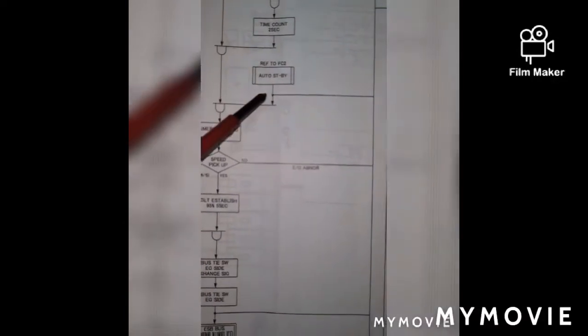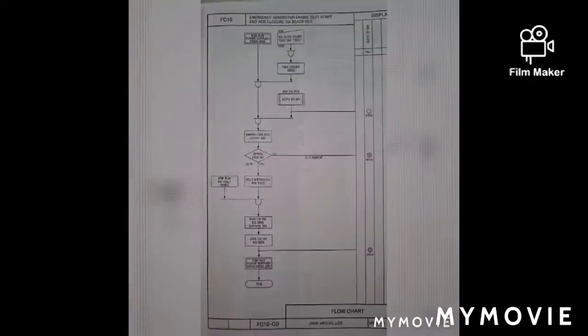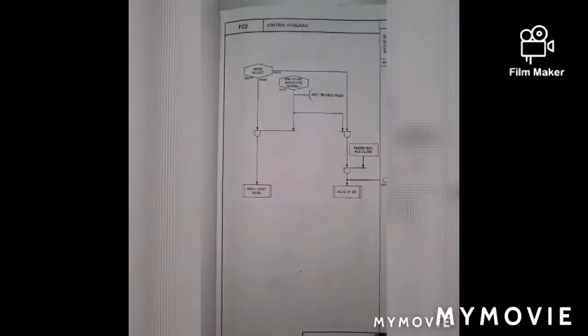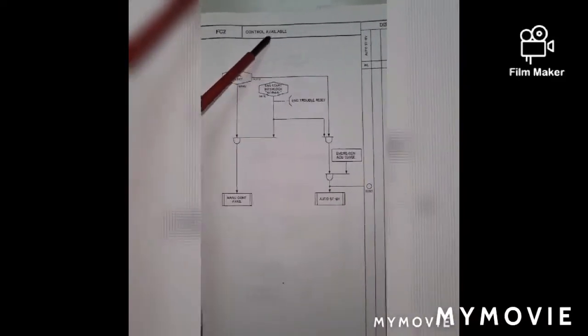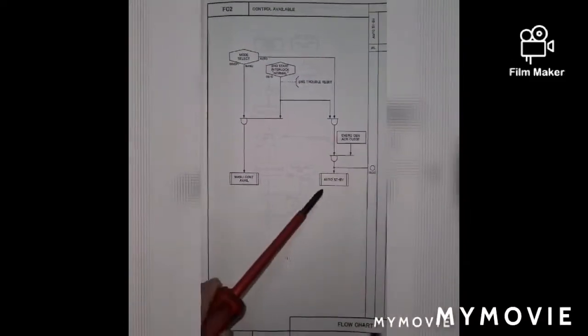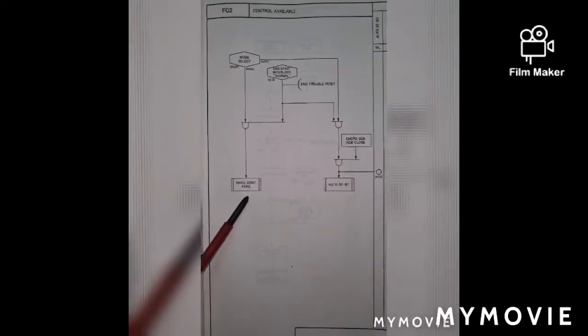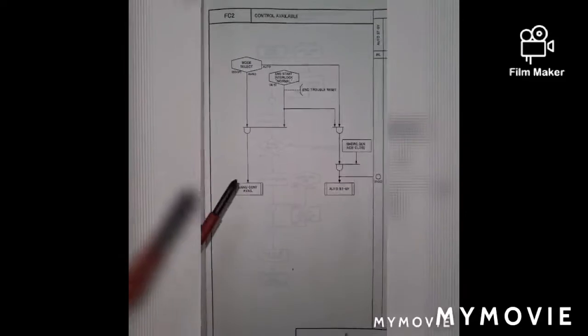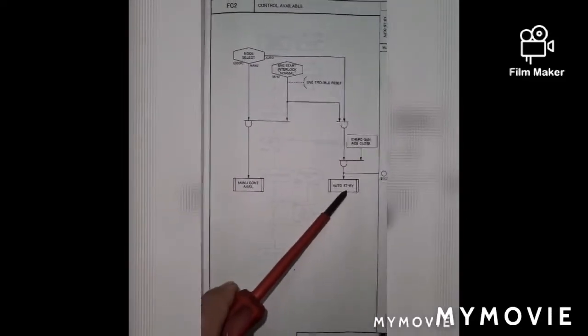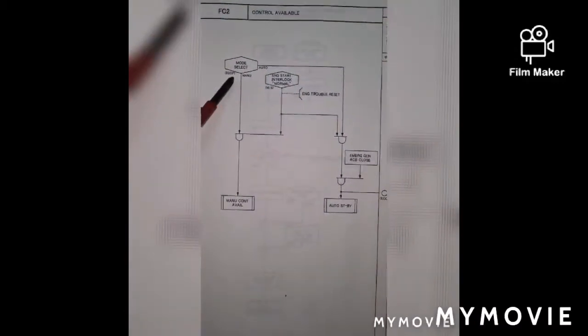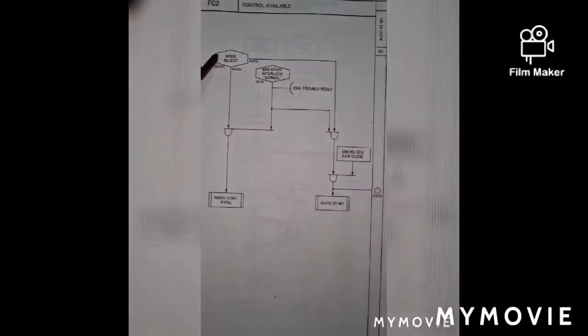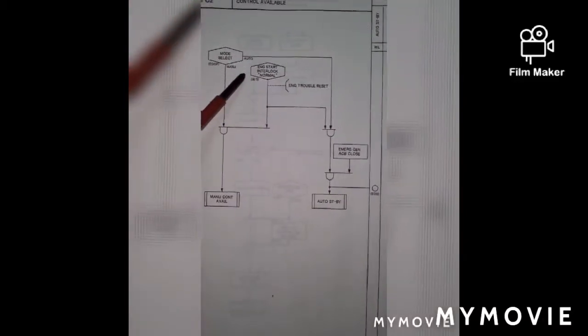As you can see here, there is the reference to FC2. This means that for FC2, you need to satisfy the condition that your emergency switchboard control and emergency generator control panel are on. This FC2 is known as the control available. These are the two options on how the emergency generator is to be started. You can start it manually, or you can start it automatically. The FC2 switch must be in auto position, and the changeover switch must be in normal position.